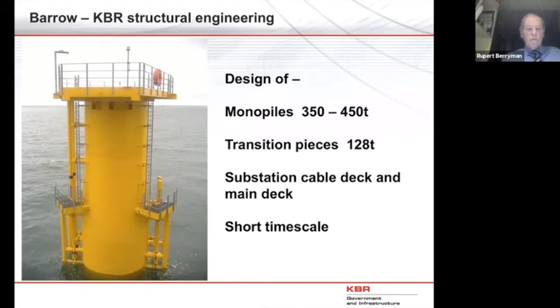We were humming and hawing about the number of transformers it should have, whether it should have 2 or 1. But the client in the end said, we just want 1. There's always a chance that a transformer might blow up. And we thought, well, if there are 2 transformers up there and one of them blows up, it might damage the other one. So we might just as well have one big one up there to start with. So that's a 132 kV transformer.